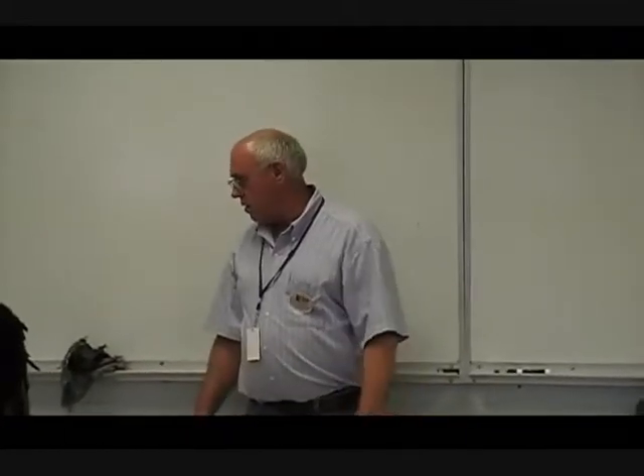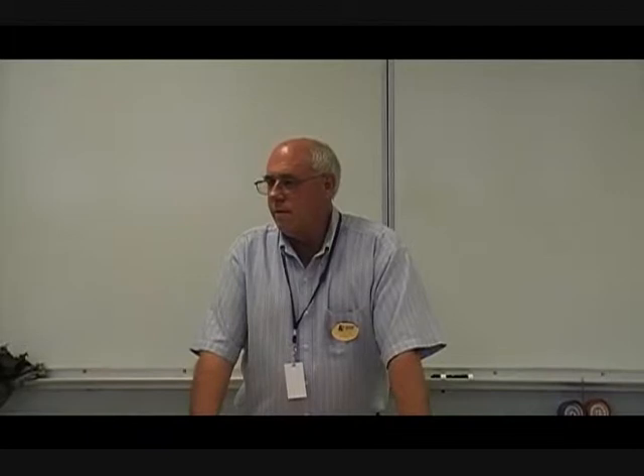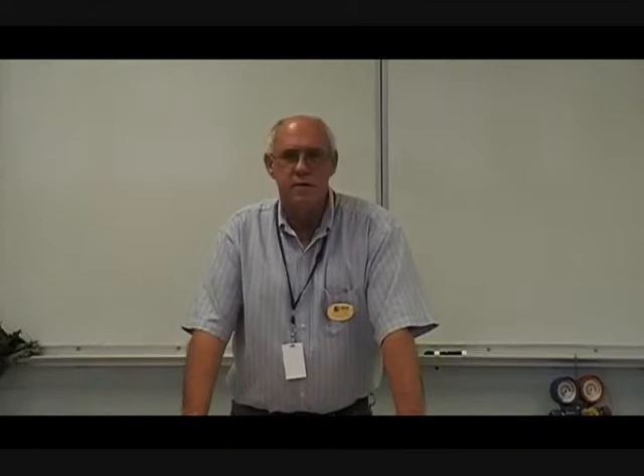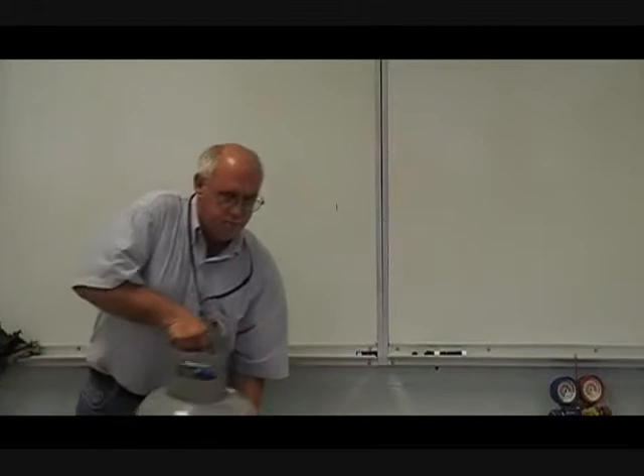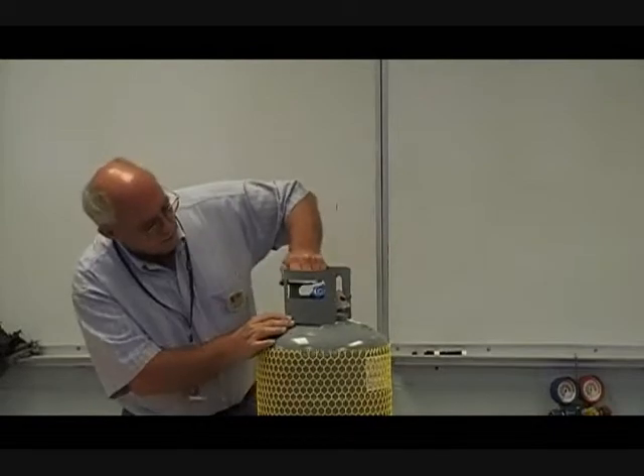Why can't we use a regular refrigerant cylinder? You can't refill it — there are some pretty hefty fines associated with that. If you look at how the recovery cylinder is made, it's much heavier material. It also has retest dates and tare weight on it — a lot of information. You'll be going through this in your C1 lab in the very near future.